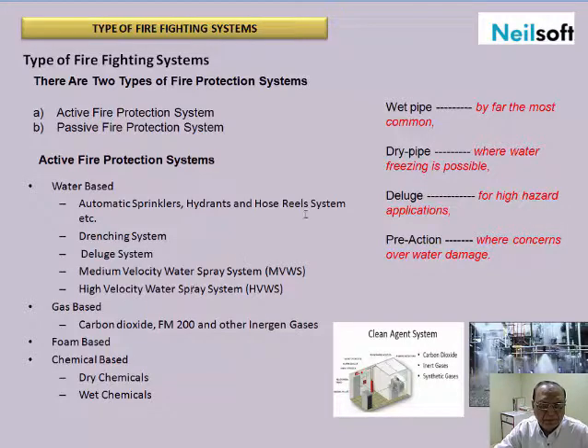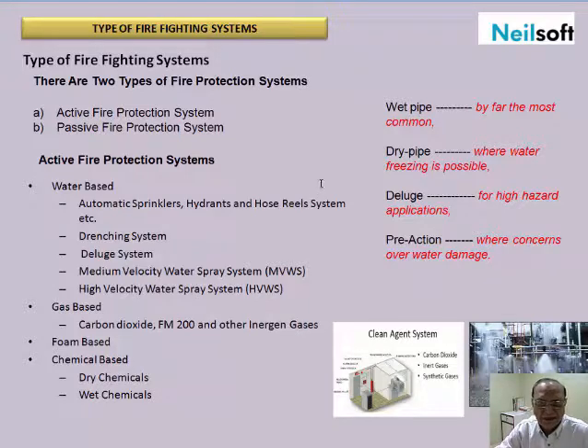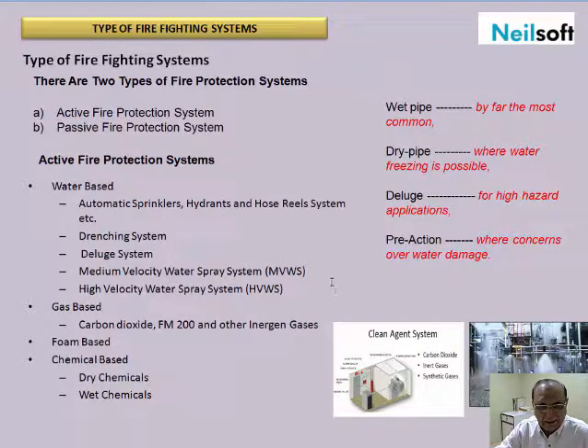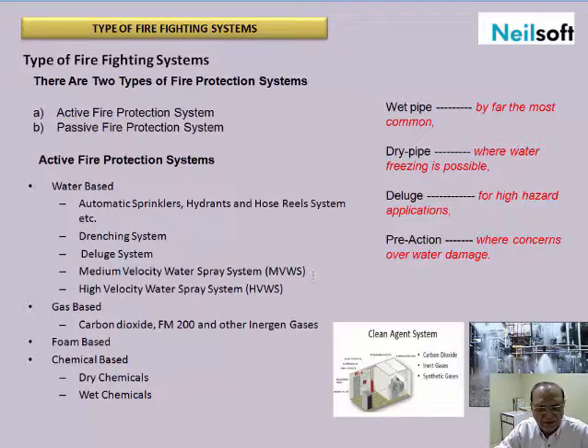Active fire protection systems are categorized as water-based, which includes automatic sprinklers, hydrants, and hose reel systems. Drenching systems are used for cooling surfaces. Deluge systems discharge water from open nozzles for different applications. These firefighting systems are further categorized into medium velocity water spray systems and high velocity water spray systems.